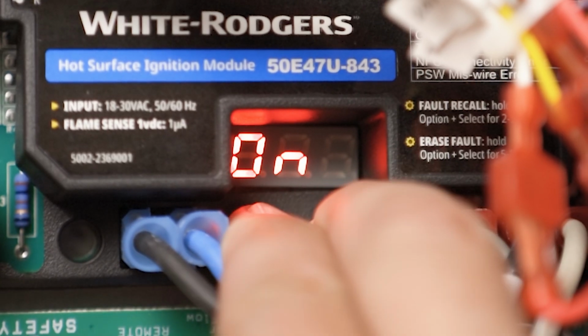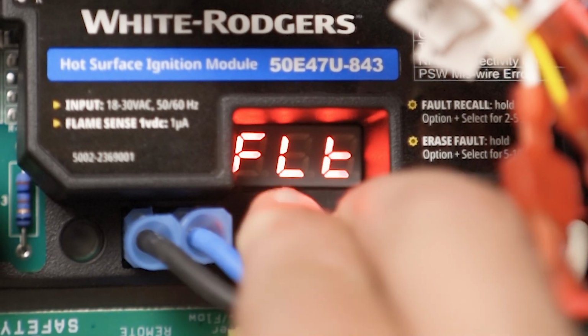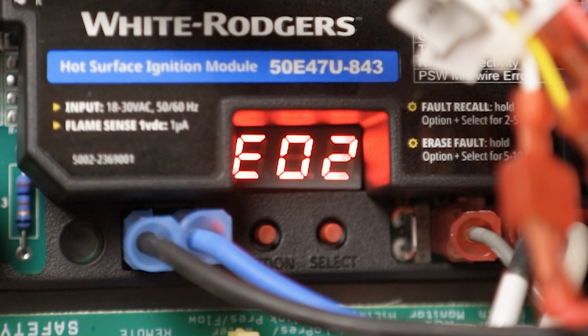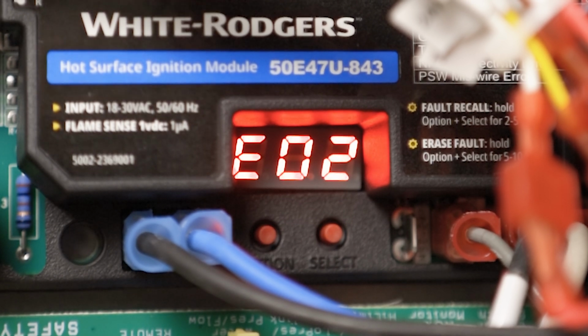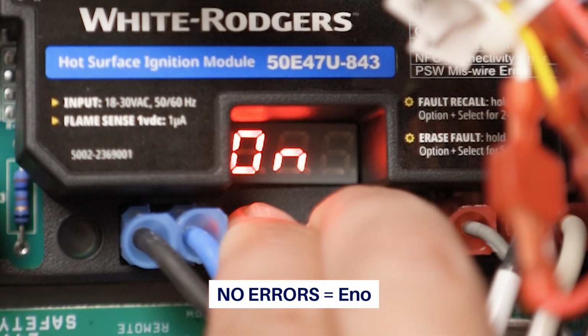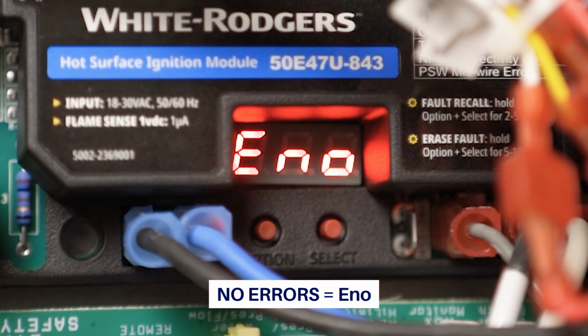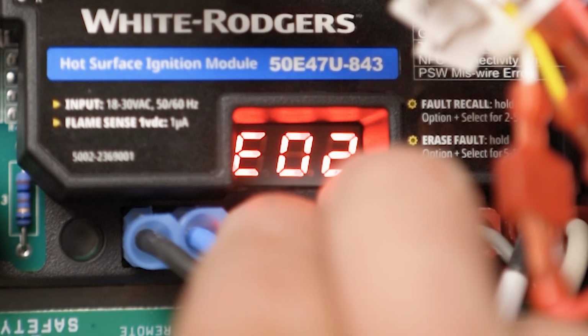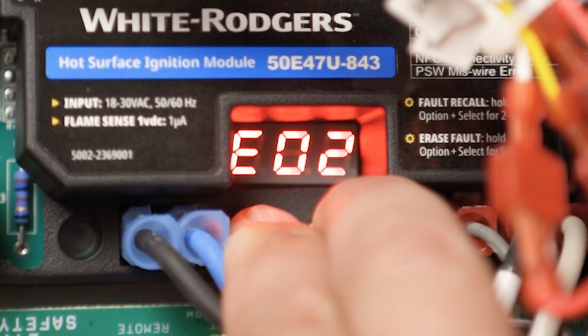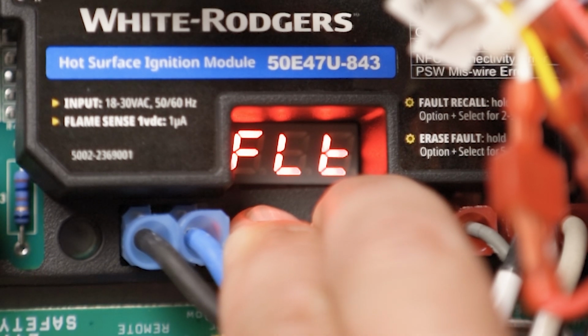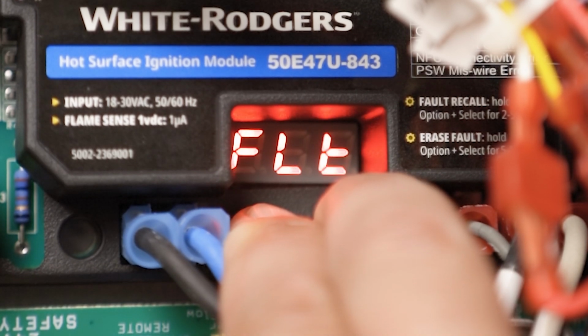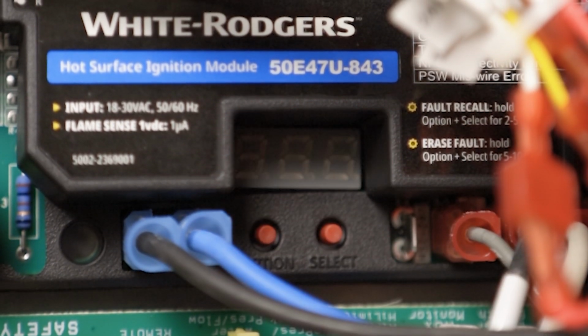Fault codes can be accessed on the module anytime the module is powered. Press the Option and Select buttons at the same time for 2 to 5 seconds. If there are no errors, the display will read ENO. To clear errors using the module, push Option and Select at the same time for 5 to 10 seconds. This action can be performed whenever the control is powered on.